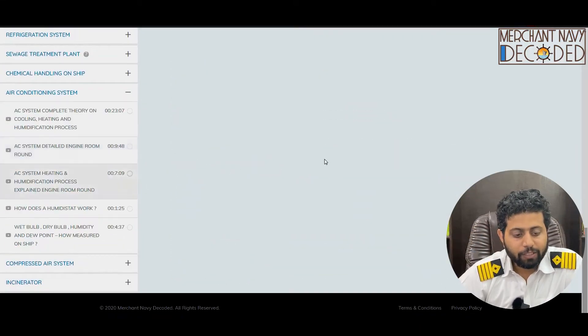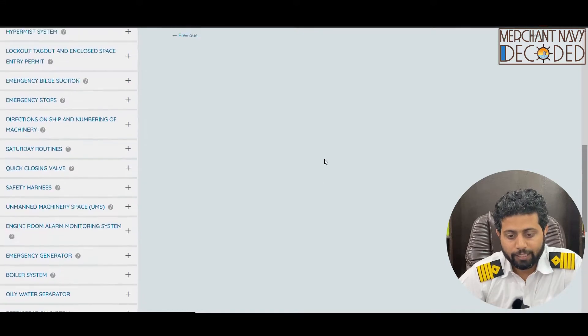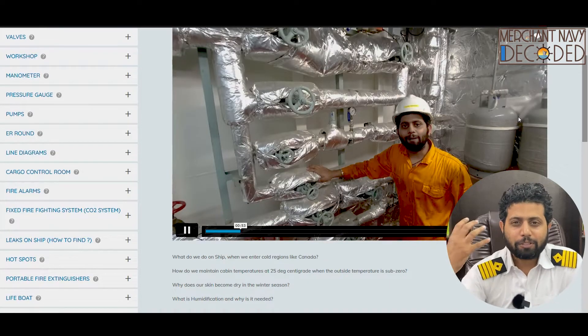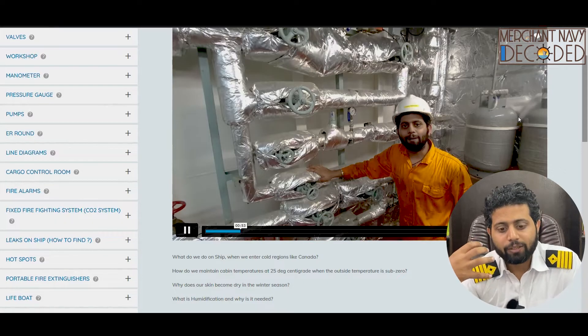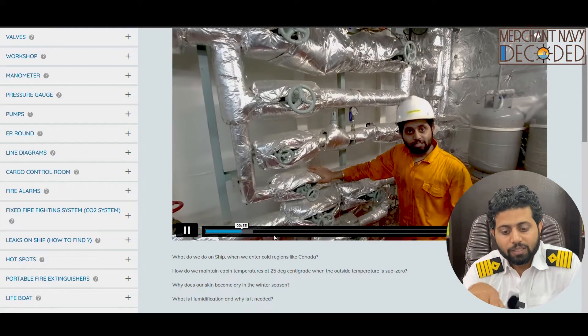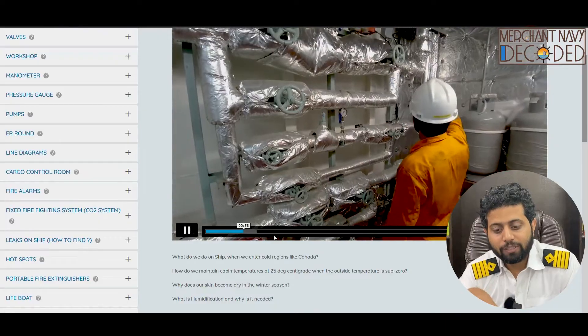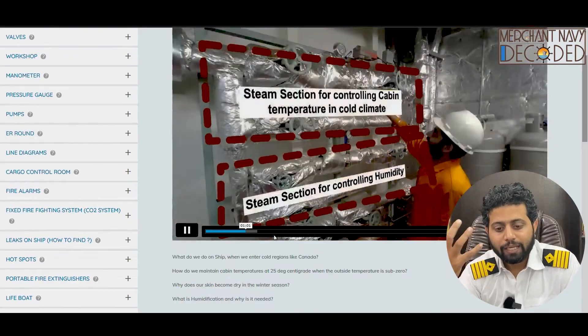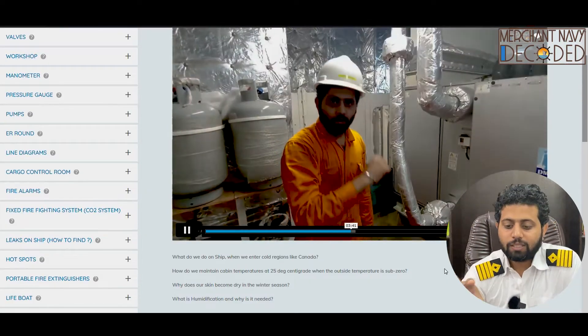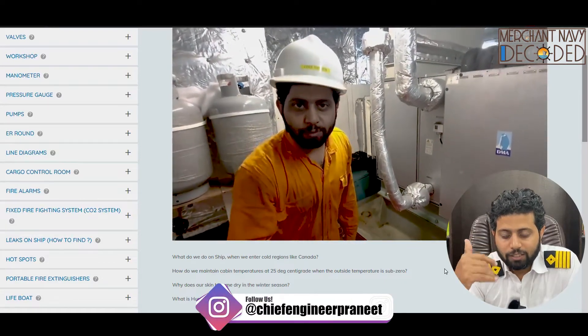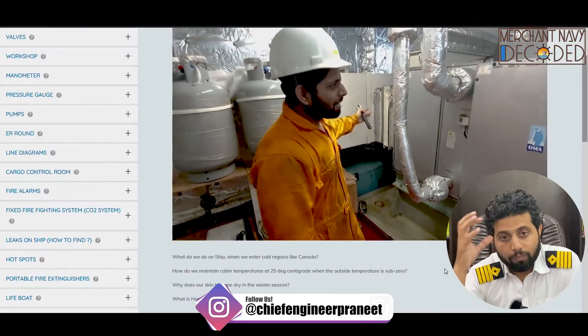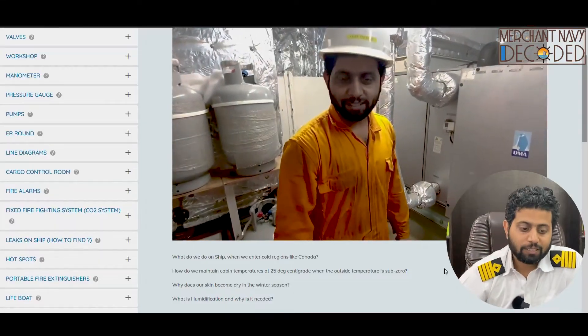Next is the AC system heating and humidification explained with an engine room round. In this video, the heating part is shown live — suppose you are in Canada with a temperature of minus 20 degrees centigrade outside, how do you heat your cabins through steam heating? What is the humidistat there for? This is the steam heating line, and I explain how it goes into the AC system and heats the accommodation, covering the AHU (air handling unit) section, where the steam goes and returns, and where the humidification steam goes, why it is required, how much is required, and how it is controlled.